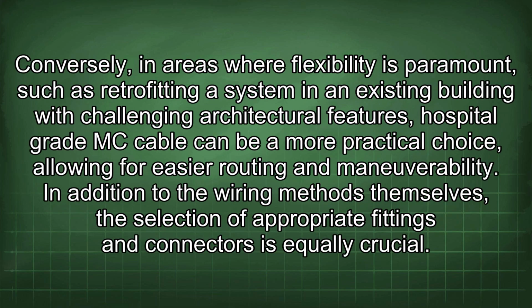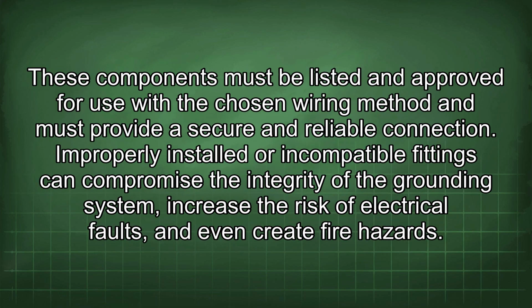Conversely, in areas where flexibility is paramount, such as retrofitting a system in an existing building with challenging architectural features, hospital-grade MC cable can be a more practical choice, allowing for easier routing and maneuverability. In addition to the wiring methods themselves, the selection of appropriate fittings and connectors is equally crucial. These components must be listed and approved for use with the chosen wiring method and must provide a secure and reliable connection. Improperly installed or incompatible fittings can compromise the integrity of the grounding system, increase the risk of electrical faults, and even create fire hazards.